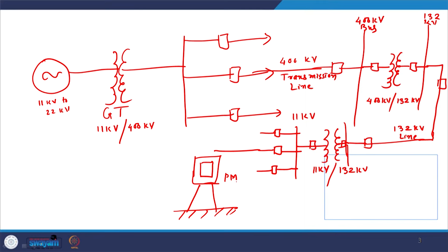These consumers are called HT consumers, and from this the power is received by another transformer, that is known as the pole mounted transformer. This is your pole mounted transformer where the power is available. In the pole mounted transformer you have 11 kV on one side, and on the other side you have 415 volt. From 415 volt you have a number of distributors.